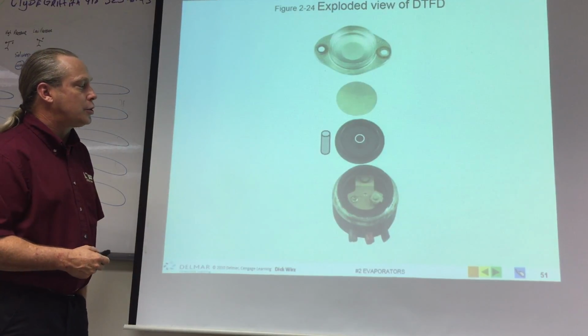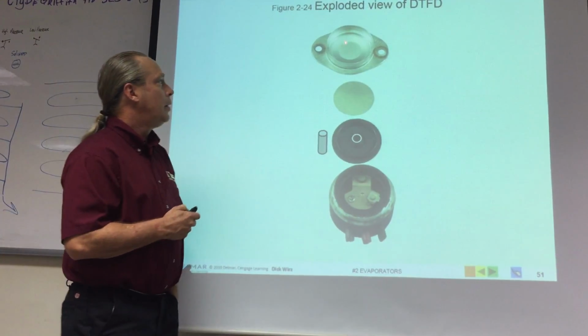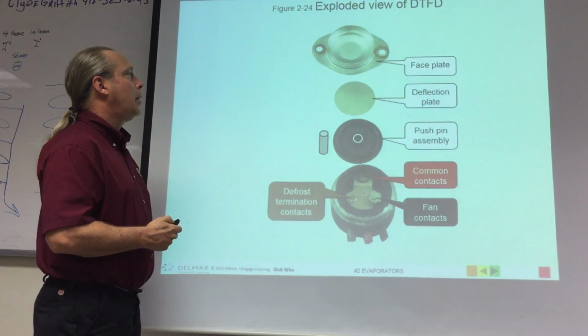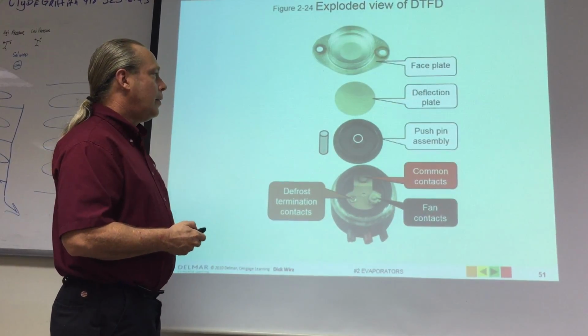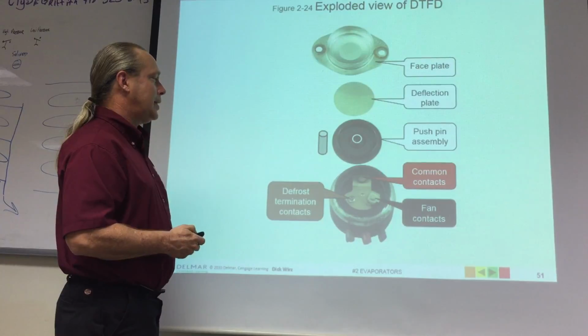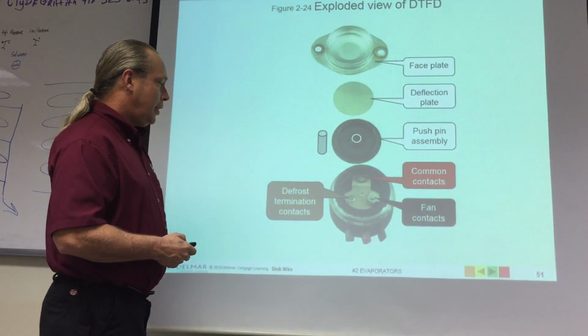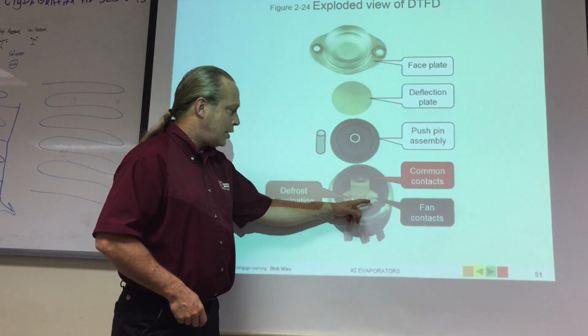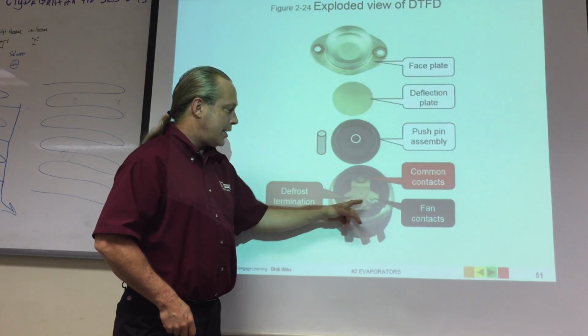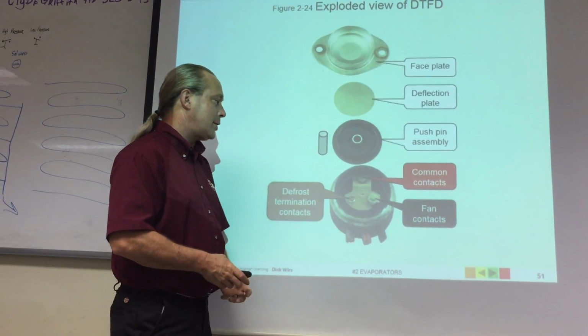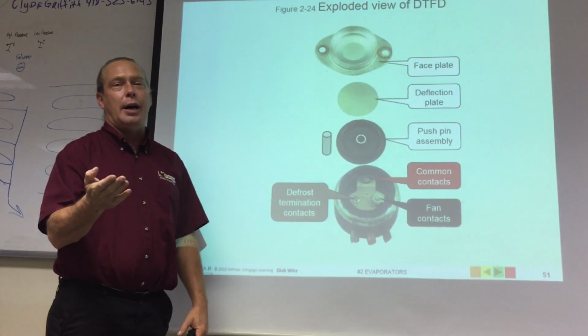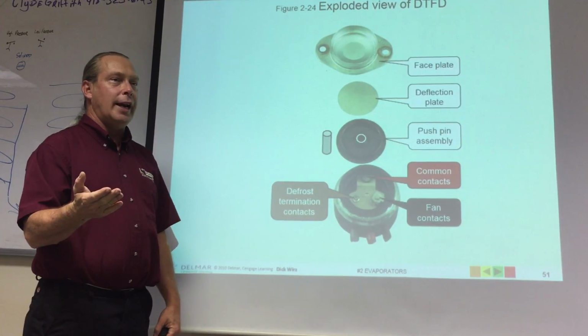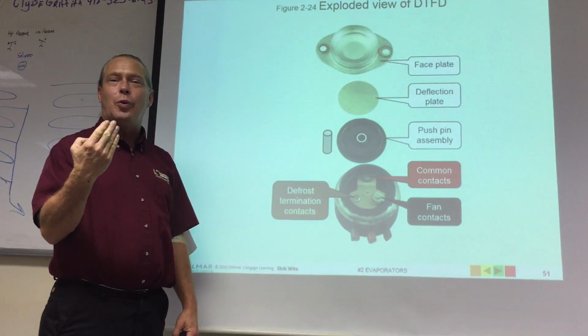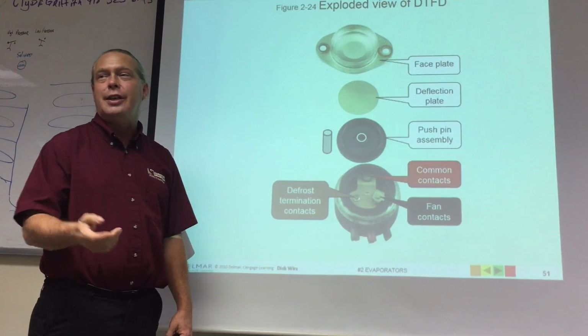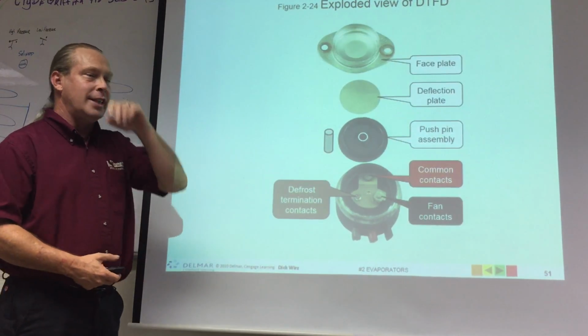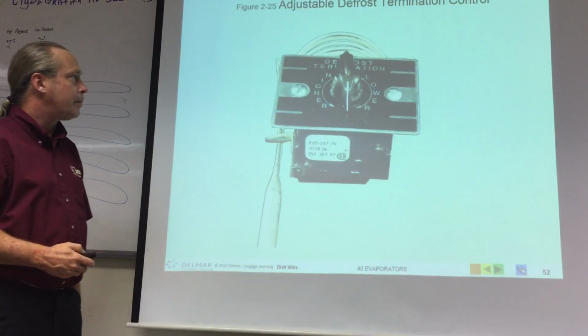And here's the basic construction of the thing. We've got our face plate, the deflection plate, the push pin assembly, and you can see this thing has two contacts. A contact on top and a contact on bottom, being that it's a bimetal element. When it gets warm, it's gonna flex one way. When it gets cool, it's gonna flex the other way. It's just that simple of a device.